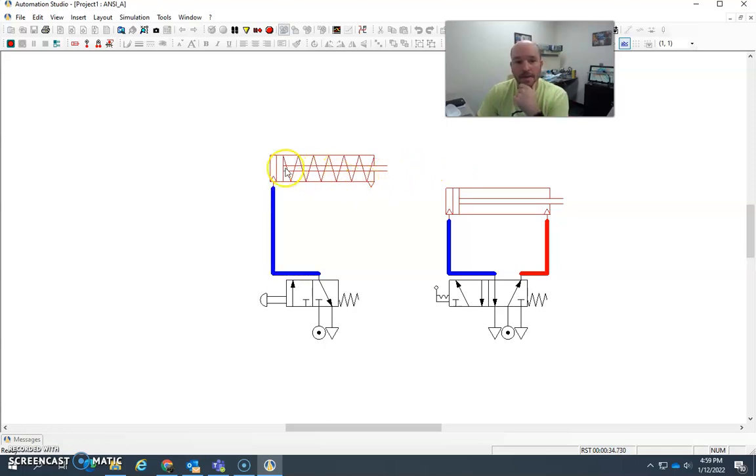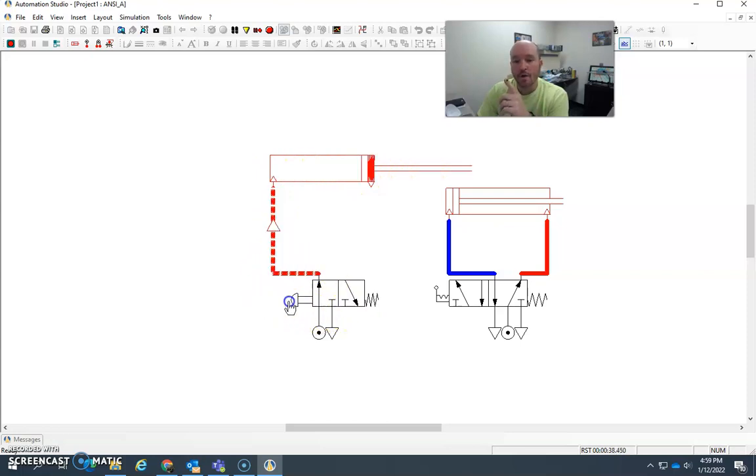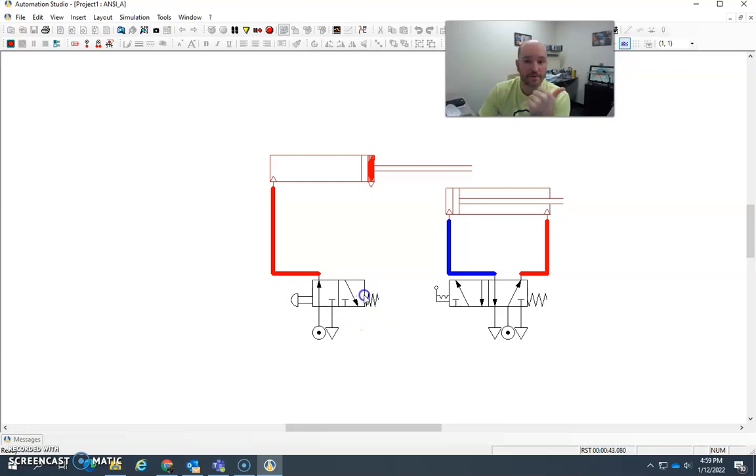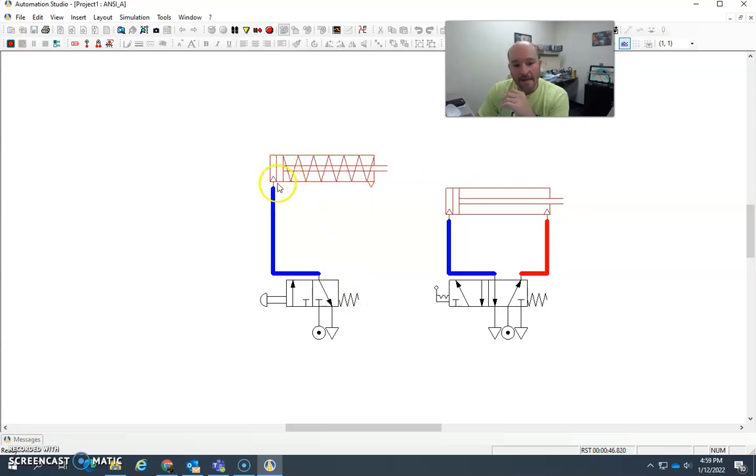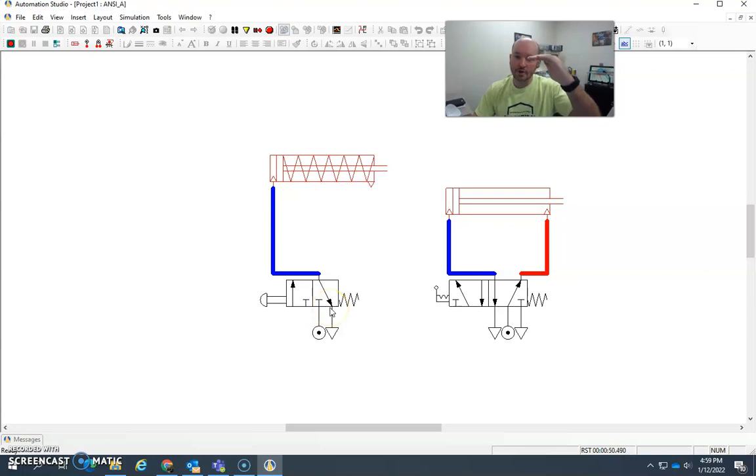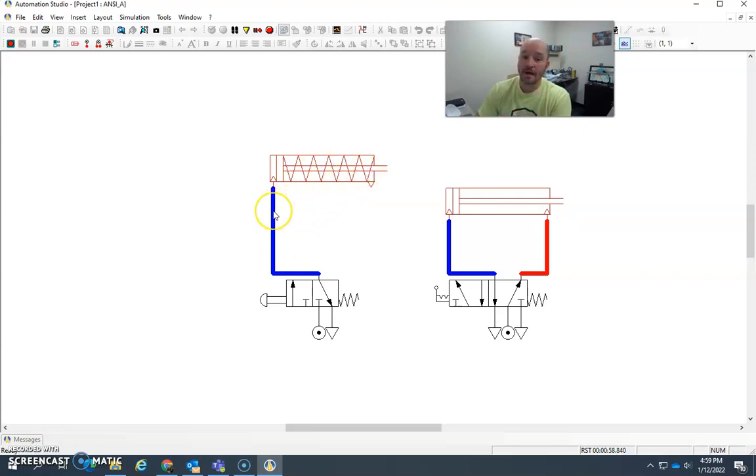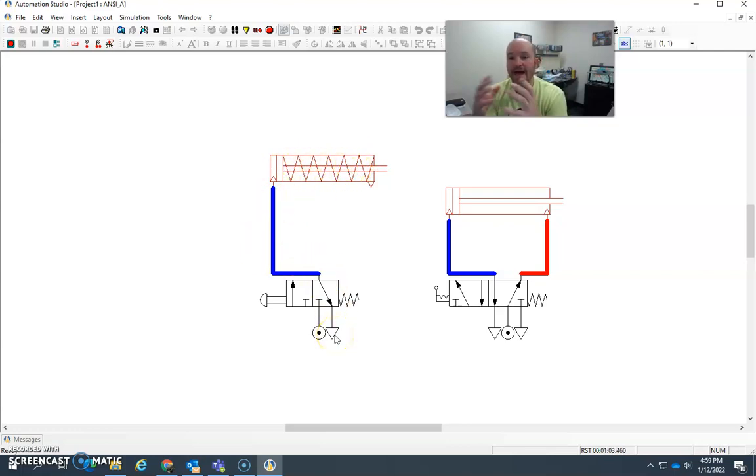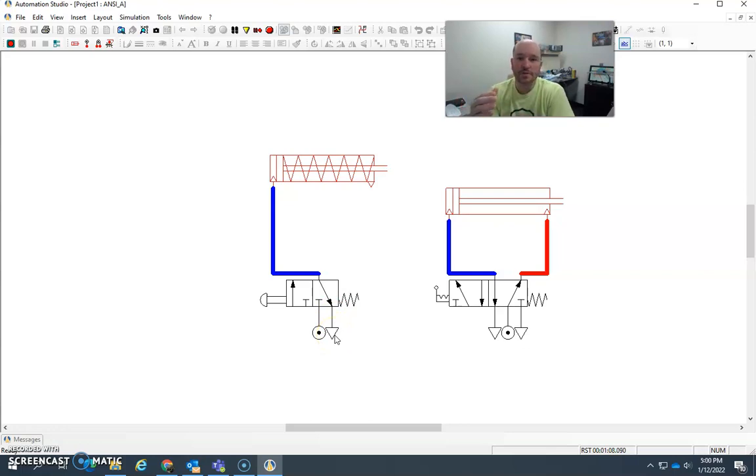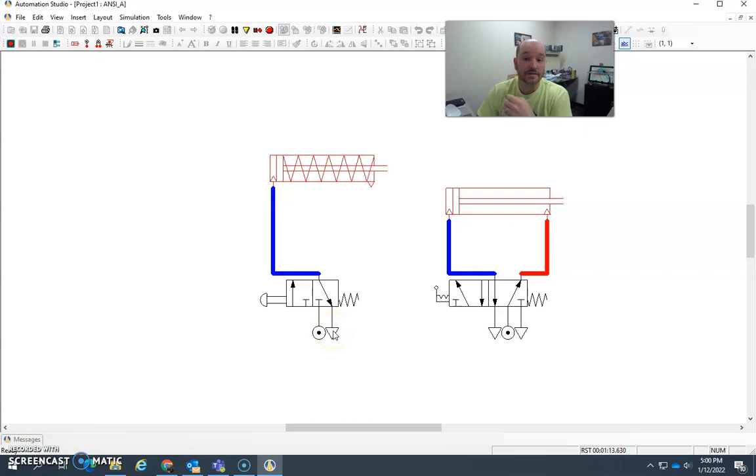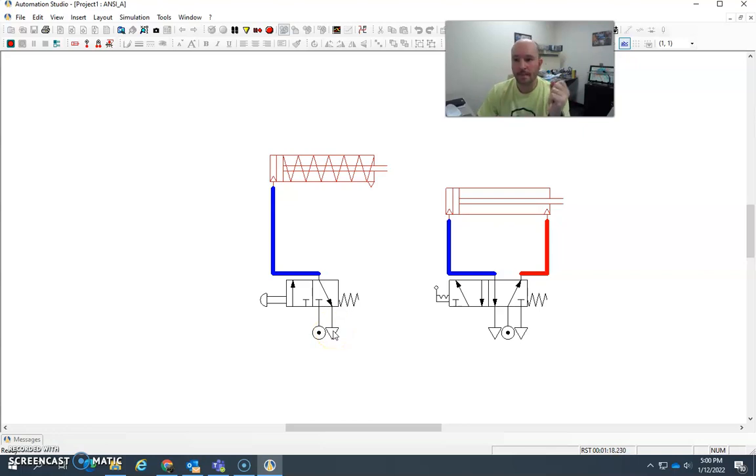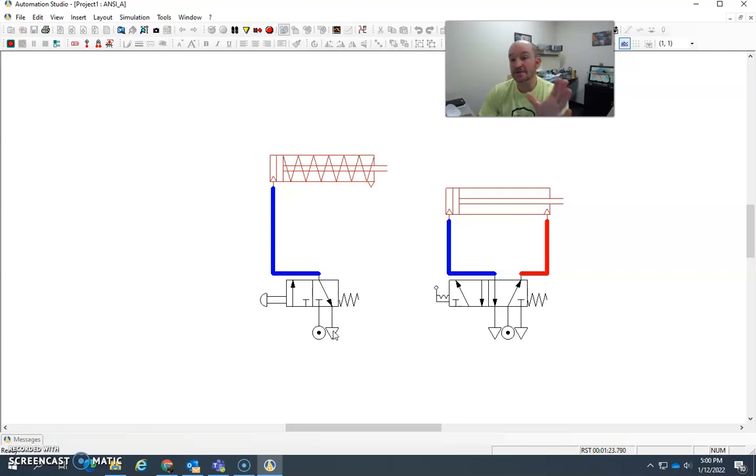So when I let it go, the air will flow down back through here. Because when you deactivate the button, this spring will shift the spool back to its normal position. And the air then can flow out because the pressure in here drops down to zero because this is now exposed to atmosphere. So then you have higher spring pressure than air pressure, and that spring pressure forces the air out, and then it's evacuated into the atmosphere. In most situations, there may be some situations in some FDA-regulated facilities where this cannot happen, where you can't just simply exhaust it out. But most of the time, you'll just hear a noise like pssst, pssst, pssst.